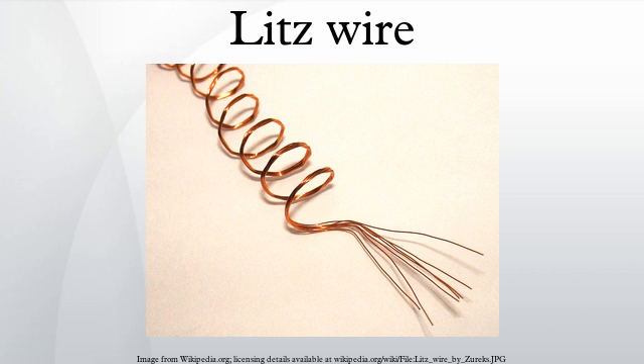For AC at frequencies high enough that the skin depth is small compared to the conductor's size, the skin effect causes most of the current to flow near the conductor's surface. At high enough frequencies, the interior of a large conductor does not carry much current. At 60 Hz, the skin depth of a copper wire is about 1/3 inch. At 60,000 Hz, the skin depth of copper wire is about 0.01 inches.